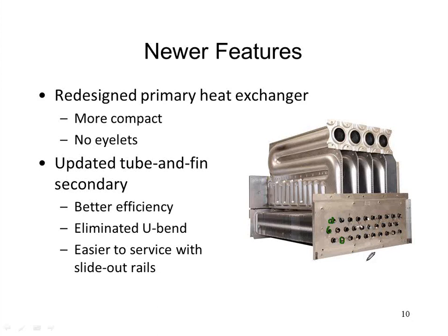If you were to pull that tab out, it would be a corkscrew piece of metal. And the whole idea with that is as the gas is flowing through these tubes, that corkscrew piece of metal is causing the gas to mix around, and hence the gas touches the outside of the tube more frequently and transfers a little bit more heat. So just kind of scrubbing a few tenths more efficiency out of this system.